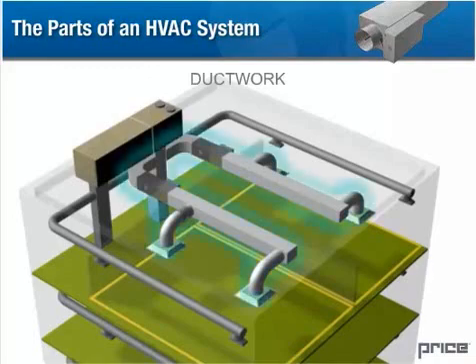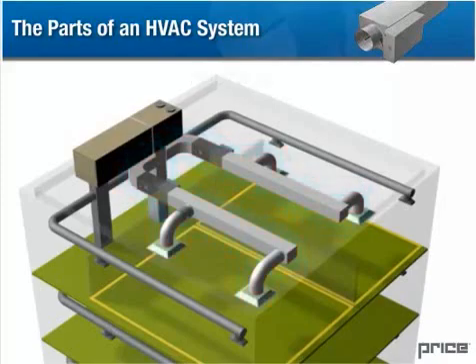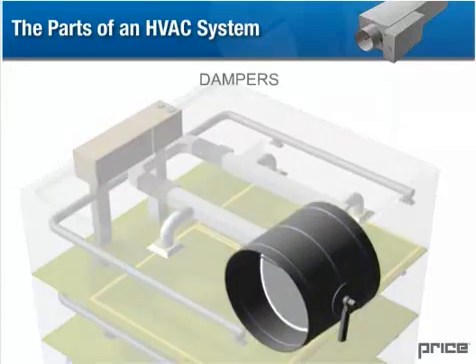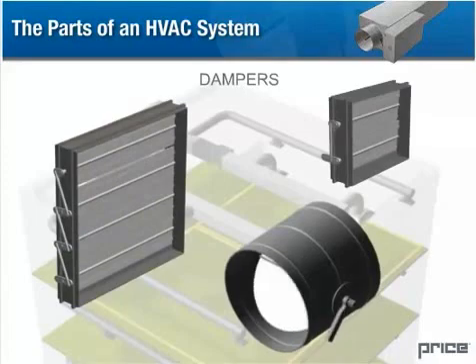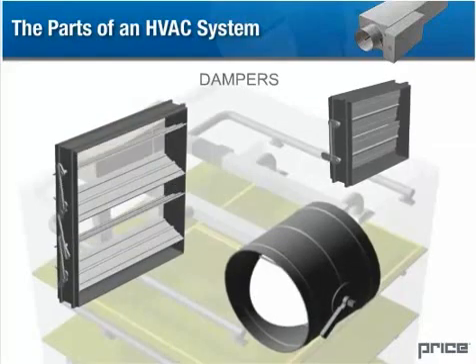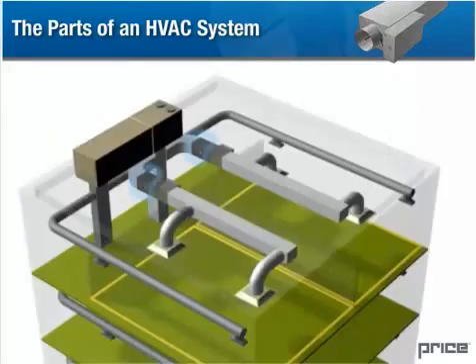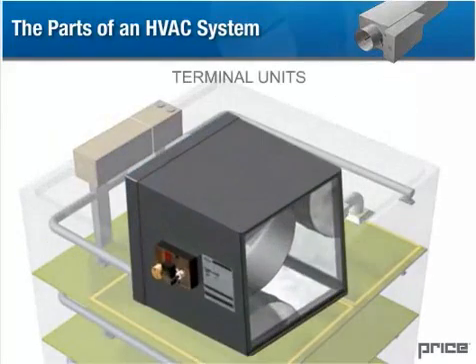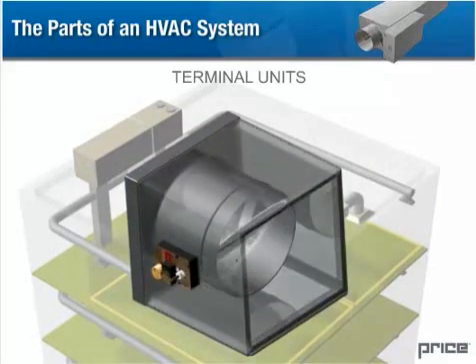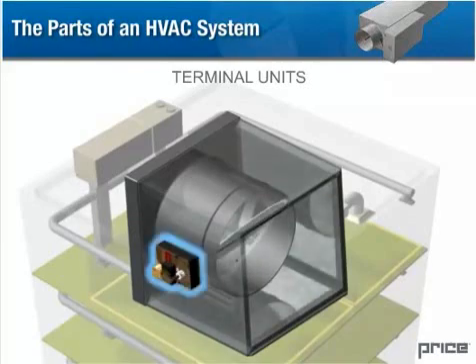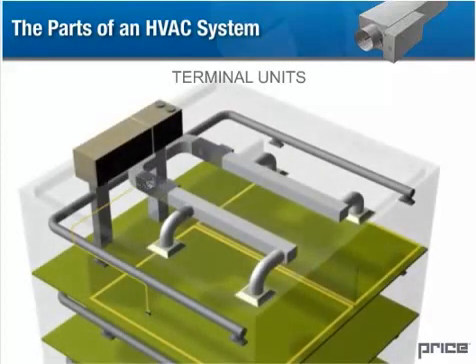Ductwork: round, square, and rectangular ductwork provides a passage for the conditioned air from the air handling unit to the environment. A damper consists of one or more blades which can be used to control the amount of airflow through a duct. Manual dampers are used to ensure that different parts of the building receive proportional ventilation based on area and demand. Automated dampers may be installed at firewalls, which close in the case of a fire. A terminal unit is a device that uses an automated damper to control the amount of air which is delivered to a room or region. The damper is typically controlled by an electric, pneumatic, or digital actuator, which in turn is regulated by a thermostat.